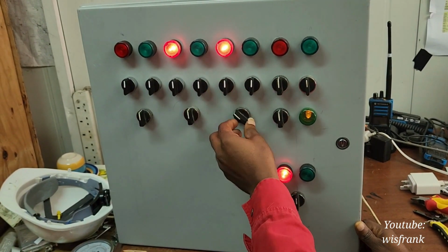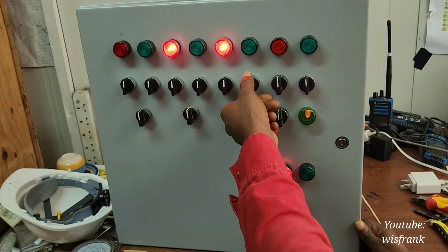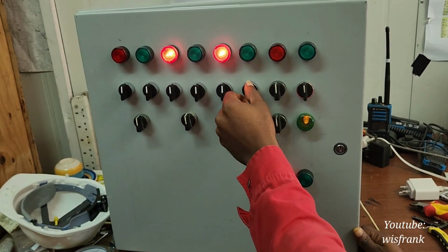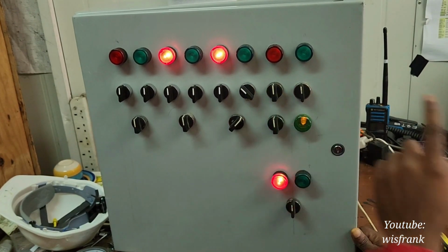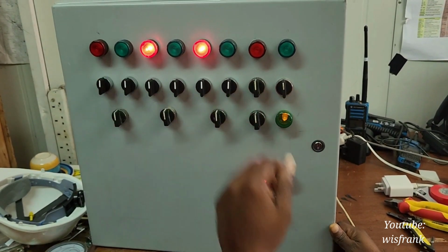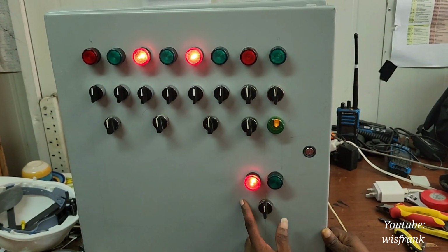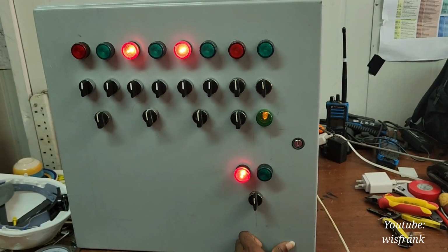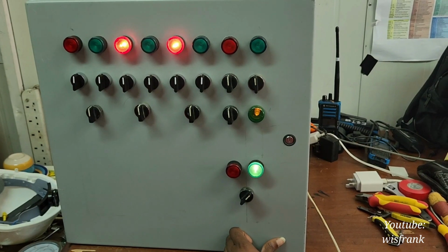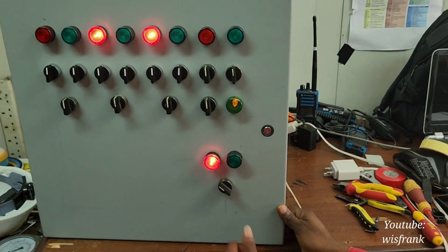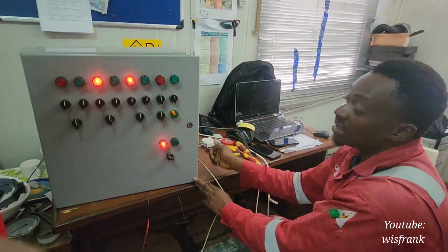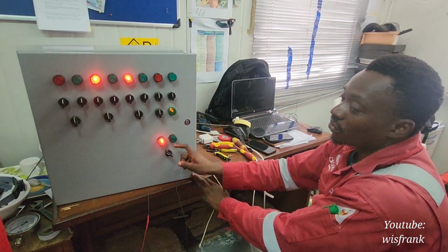Okay, let's turn this off and let's go to pump B. Right here is pump B. We'll turn it to hand, it's running, and when we turn it from manual to auto, it will not run because the terminal is not yet reached. This principle applies to every other pump here except for this one. This is our main raw water pump that comes from the borehole, and this is your run state, which is on hand, and right here is on auto. The same principle still applies also. The pressure switch needs to be activated for it to run on auto.